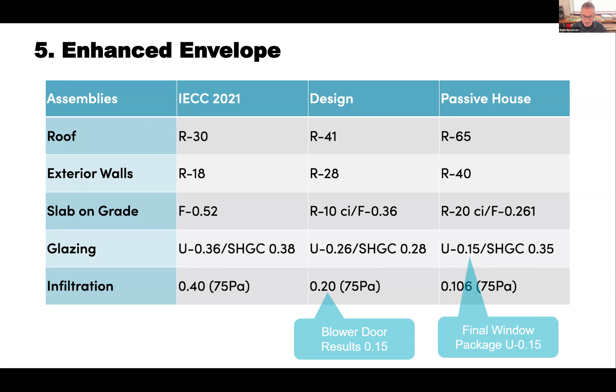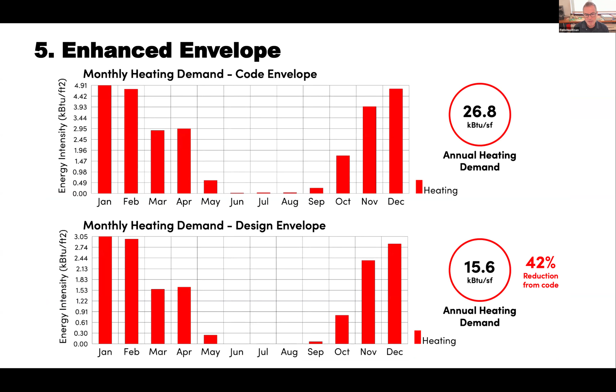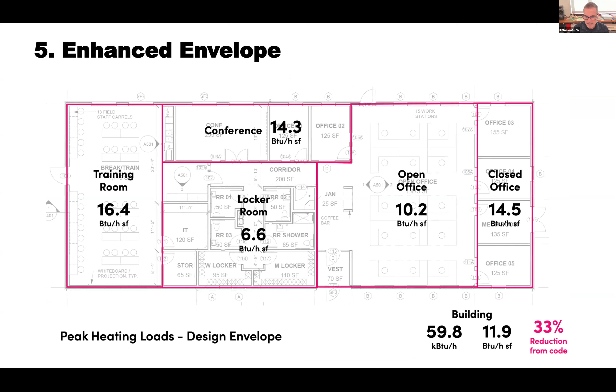Just to see what the envelope did, this is the heating demand before we applied the efficiencies of the heating system - a 42% reduction in just heating demand on the system through the envelope alone. And looking at peak loads, we saw a 33% reduction in peak heating loads on average across all the zones in the building.